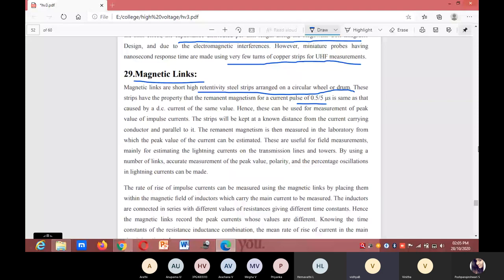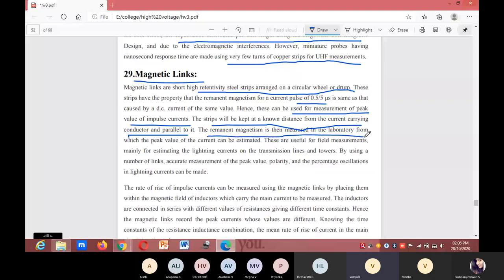Magnetic links can be used for measurement of the peak value of impulse current. These strips are kept at a known distance from the current-carrying conductor and parallel to it. The remanent magnetism is then measured in the laboratory, from which the peak value of the current can be estimated.